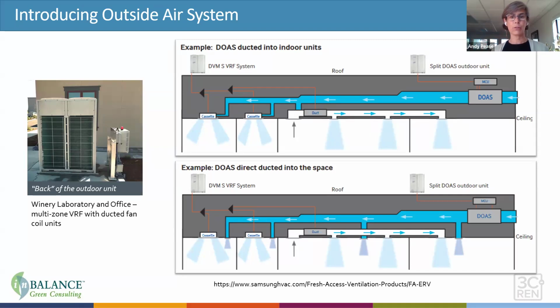With that, as we increasingly introduce outside air, it may be appropriate to decouple the heating and cooling, so we're rethinking ventilation strategies. In this example, there's a dedicated outside air system at the top, linking up via refrigerant lines into a recessed ceiling cassette or a ducted system that delivers heating and cooling, with outside air becoming part of that system for ventilation. The bottom option is a separate system altogether, so you might run fans at a time when you don't need heating or cooling at all. These approaches depend on climate, use, and application, but that's how you bring in outside air.